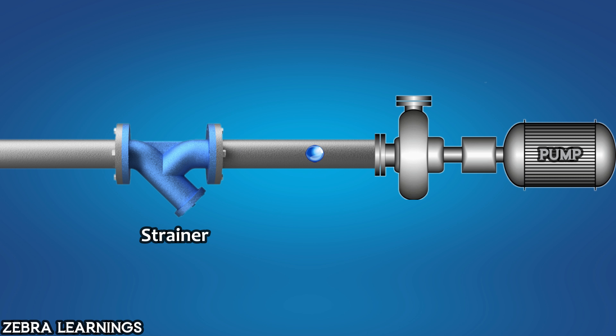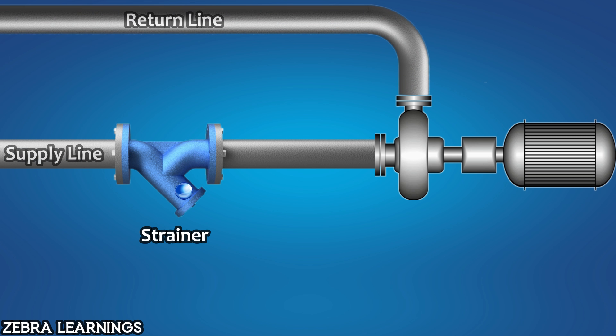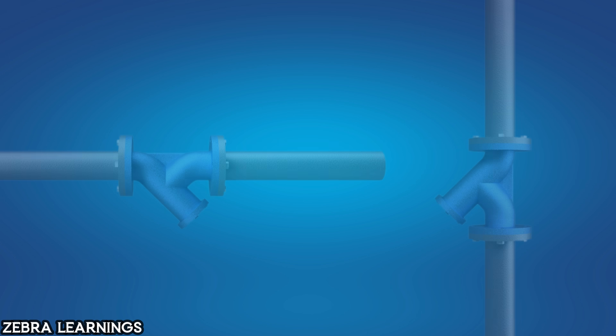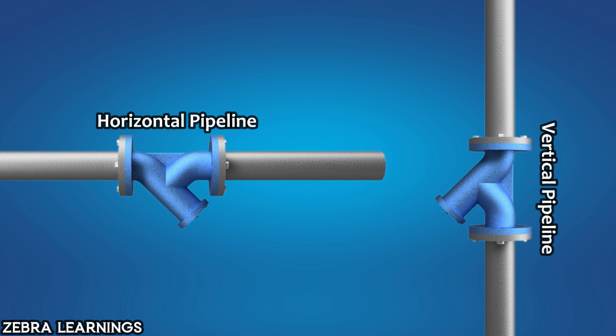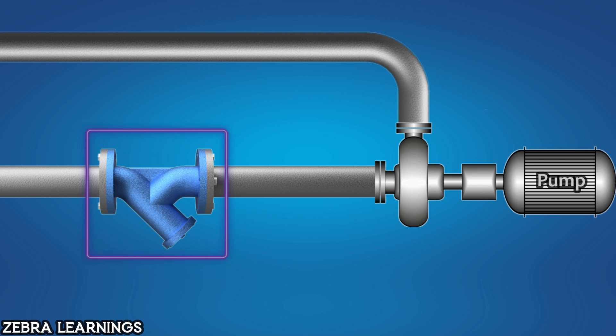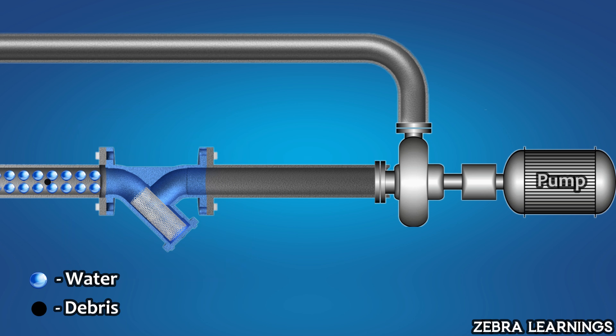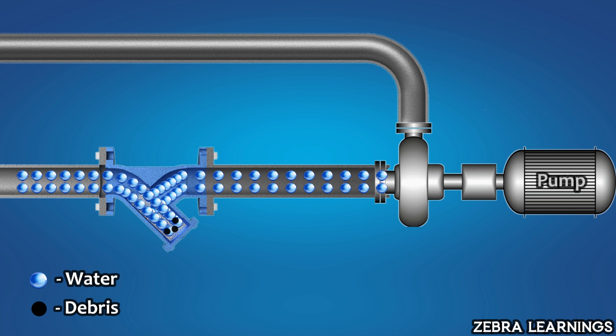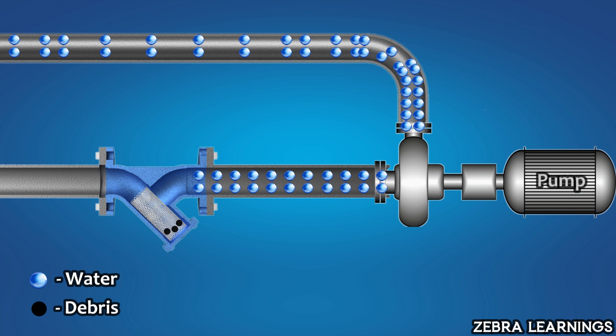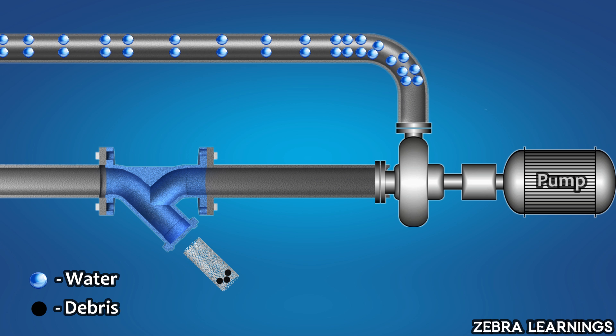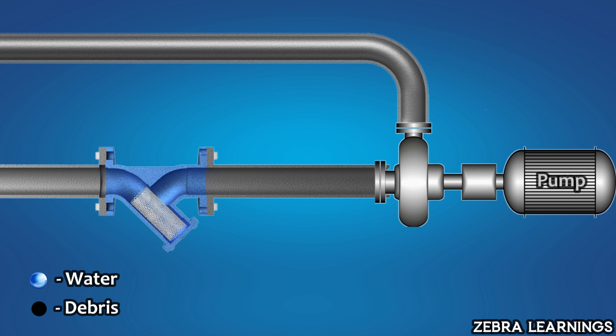Now let's understand how these two types of strainers work. Strainers are always installed in the system's supply line. We can use Y-type strainers in both vertical and horizontal pipelines. Before the water enters the system, it travels through the strainer. While traveling, all the debris in the water gets filtered with the help of mesh and stored in the strainer. The filtered water then enters the system. We can remove the mesh and clean all the particles that are stored in it. This is how a Y-type strainer works.